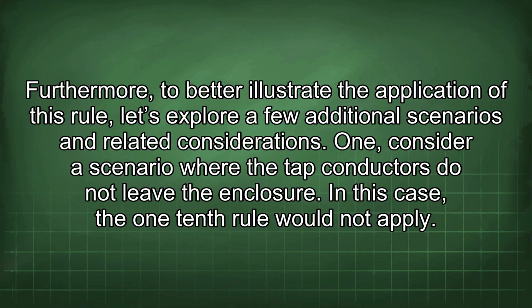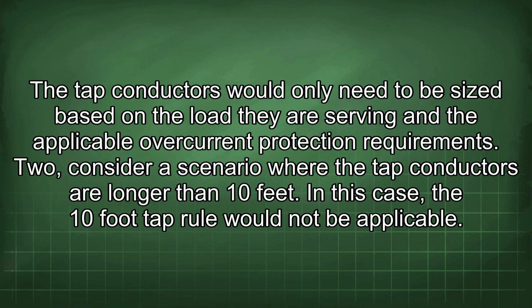Furthermore, to better illustrate the application of this rule, let's explore a few additional scenarios and related considerations. 1. Consider a scenario where the tap conductors do not leave the enclosure. In this case, the one tenth rule would not apply. The tap conductors would only need to be sized based on the load they are serving and the applicable overcurrent protection requirements.